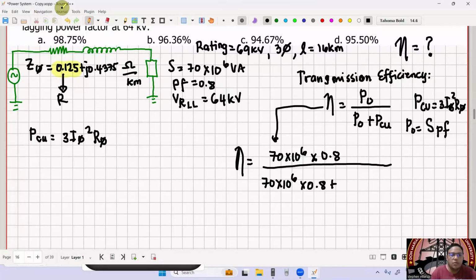So this is now equal to what? Take note, we don't have I yet here. So where do we get the I? From our S, from our load, because it dictates how much current it draws from the line. So this is now 3 multiplied by 70 mega over square root of 3 multiplied by receiving end voltage, 64 kilo.